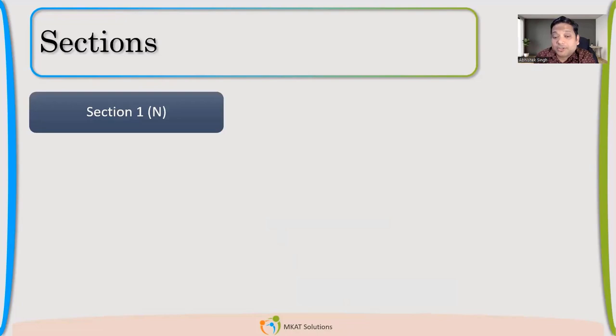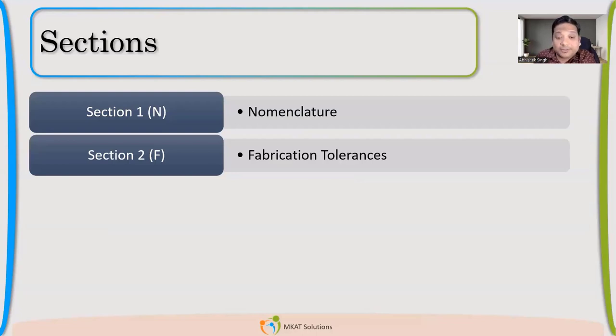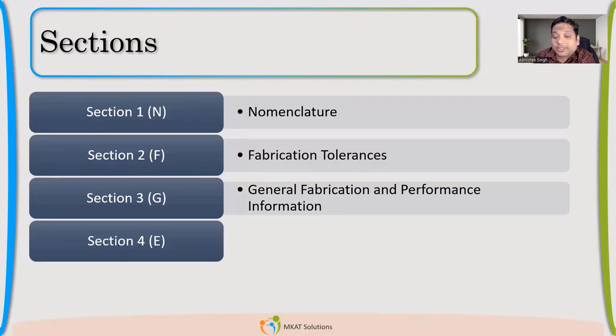Section one talks about nomenclature — it covers the nomenclature used in TEMA. Before reading any code or standard, you should be clear with the nomenclature. Section two talks about fabrication tolerances; all fabrication-related requirements and tolerances are covered there. Section three is general fabrication and performance — it includes the typical TEMA specification sheet format, nameplate requirements, and performance guarantee-related requirements.